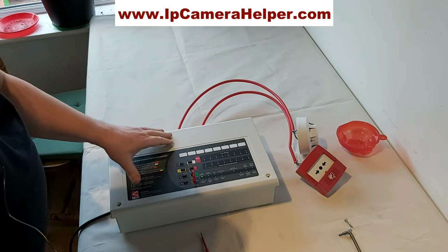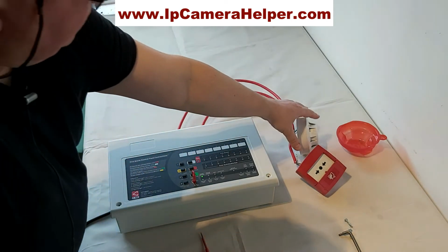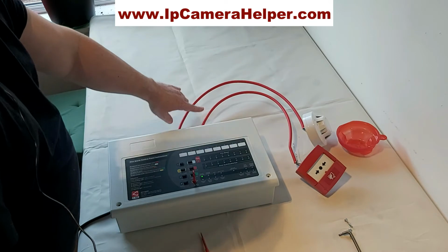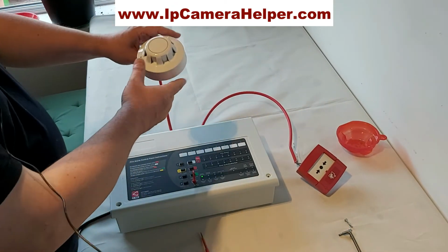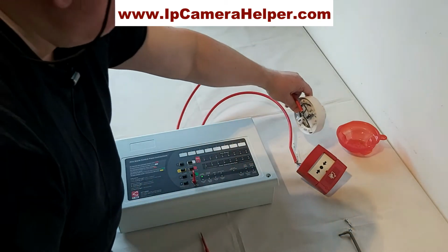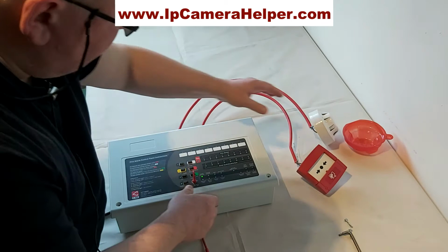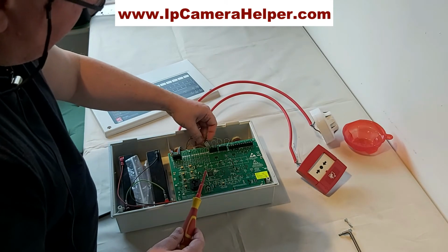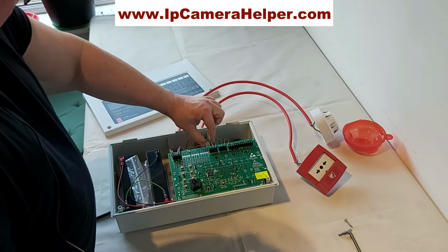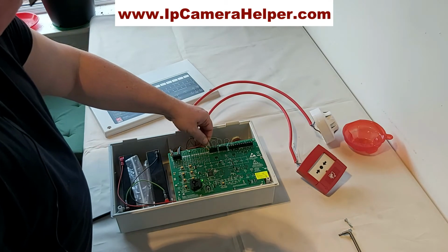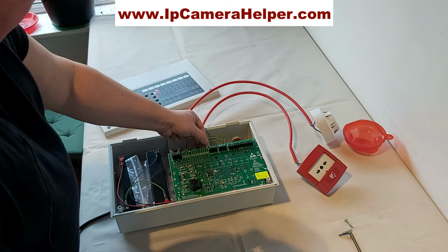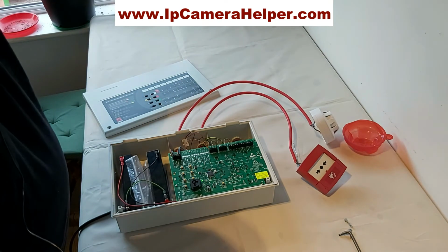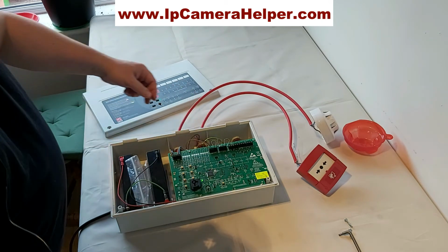So we saw the mains fault, power supply fault, device fault. There could also be other types of faults on cables. Each line of detector or siren will have an end of the line device. Just to make it easy, I will remove the end of the line device on one of the sounder lines. There are 4 of them. This one is connected. There's the end of the line. Obviously it should be on the end, but because the siren is directly connected here, I just have it here because it's easy, but this should be in the device. Usually those cables would be regular fire cable, the siren would be somewhere there, and the end of the line device, in this case a resistor, would be there.